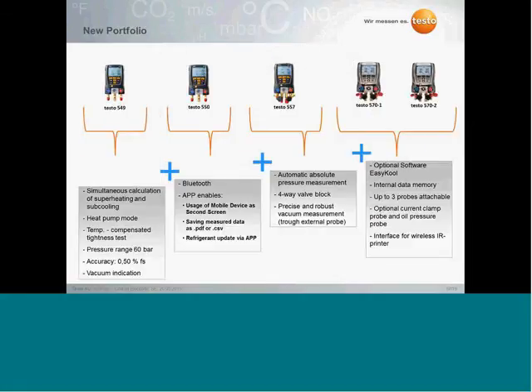In the full product range, you see the new products we just talked about on the left side, and still the two models of the Testo-570 on the right. The Testo-570 is a four-way valve block manifold which does not offer Bluetooth technology, but offers internal storage, which is a great advantage when monitoring systems over a longer period, for example 1 week or 1.5 weeks. These data can afterwards be checked, analyzed, and documented using the so-called EasyKool, which is PC-based software that can be used with the instruments.